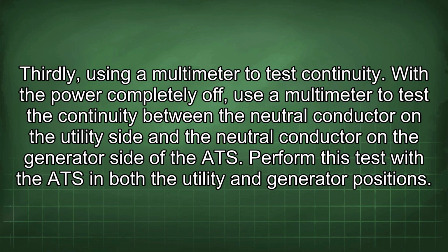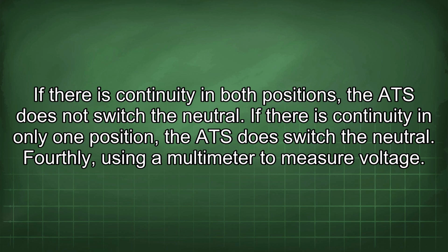Thirdly, using a multimeter to test continuity. With the power completely off, use a multimeter to test the continuity between the neutral conductor on the utility side and the neutral conductor on the generator side of the ATS. Perform this test with the ATS in both the utility and generator positions. If there is continuity in both positions, the ATS does not switch the neutral. If there is continuity in only one position, the ATS does switch the neutral.